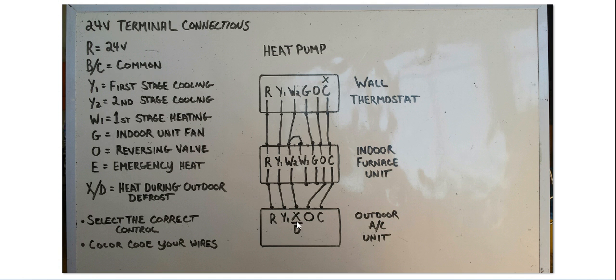All right? So R, Y1, X, D, O for reversing valve. And that's your common C. All right? So this is how you would wire up a heat pump. All right? And that's about it. Okay? You follow this and you're not going to have much of a problem wiring up heat pumps.